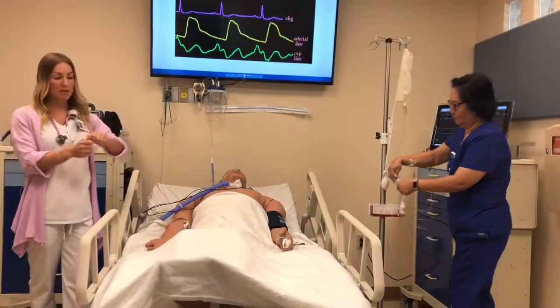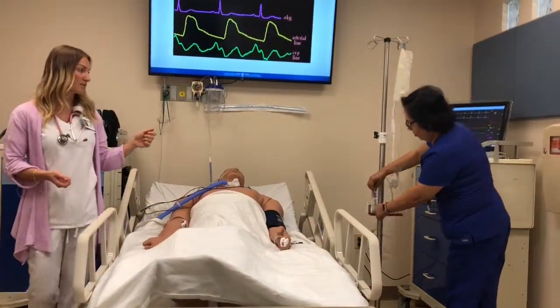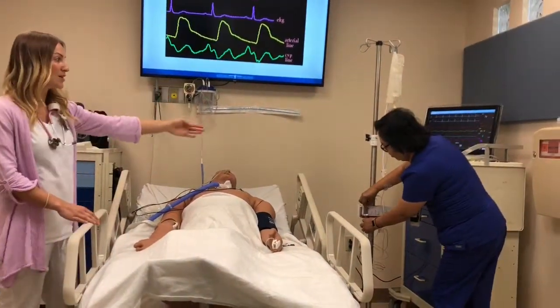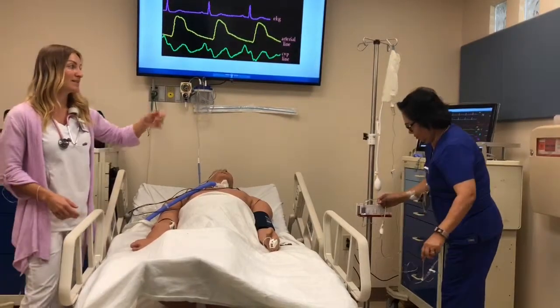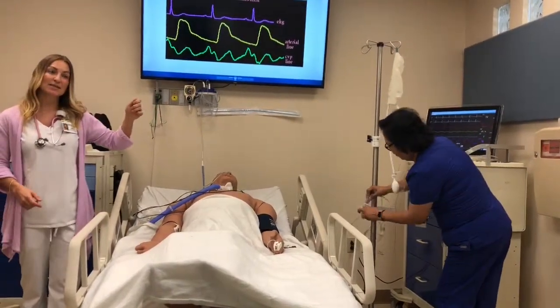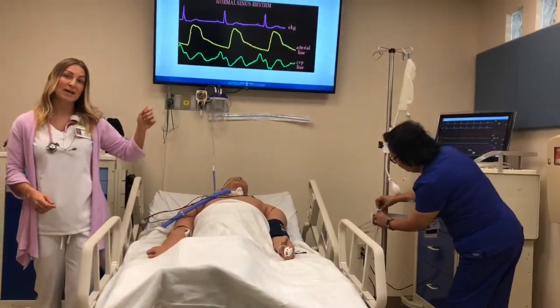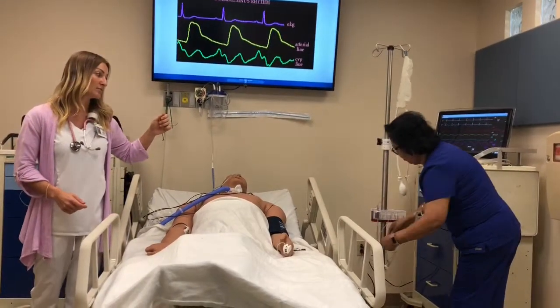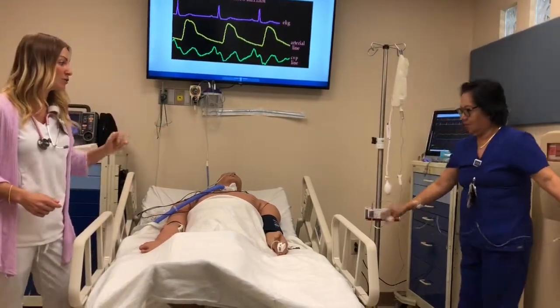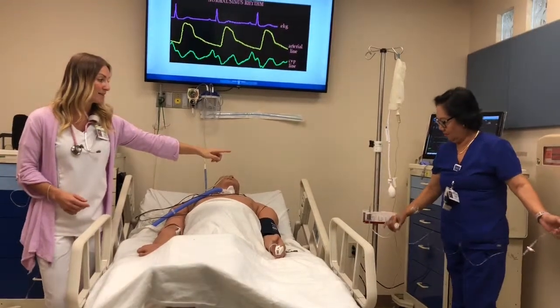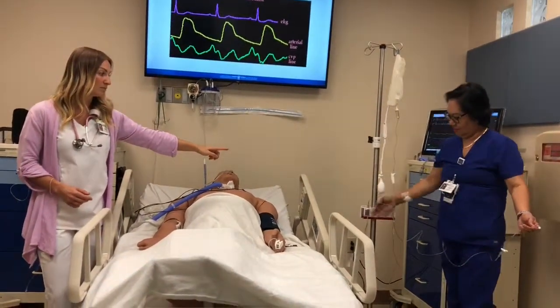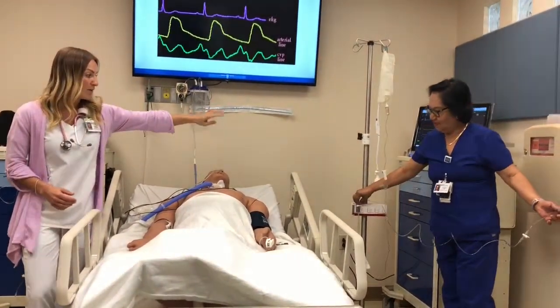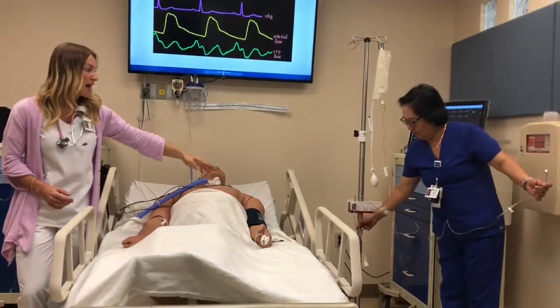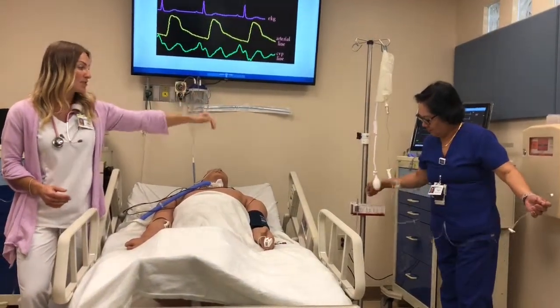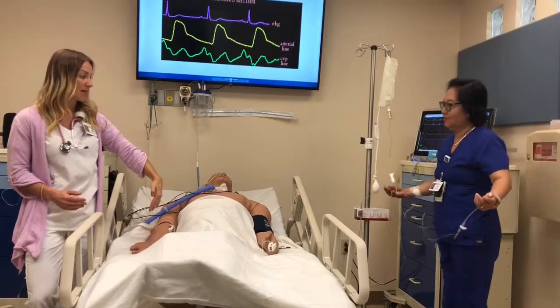Next, we're going to open up our transducer pack, revealing what you see there. One end is going to have a spike. That spike is going to go into the normal saline bag that is currently pressurized. Halfway down the line, you're going to see the actual plastic transducer component. And then farther down the line, you're going to see how it goes to the patient, and down goes the tail that's going to be the cable.